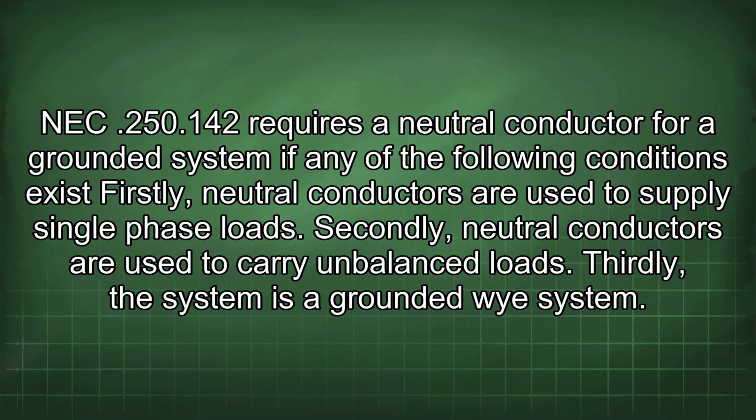NEC 250.142 requires a neutral conductor for a grounded system if any of the following conditions exist. Firstly, neutral conductors are used to supply single-phase loads. Secondly, neutral conductors are used to carry unbalanced loads. Thirdly, the system is a grounded Y system.